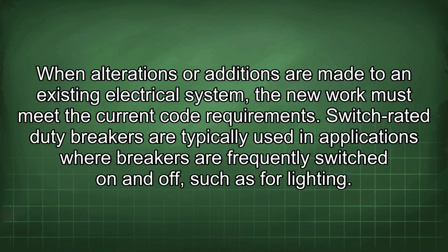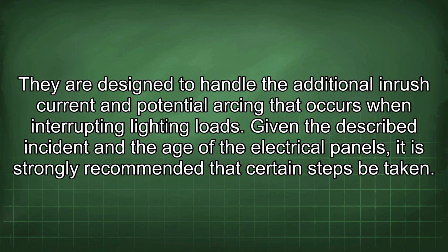Switch-rated duty breakers are typically used in applications where breakers are frequently switched on and off, such as for lighting. They are designed to handle the additional inrush current and potential arcing that occurs when interrupting lighting loads. Given the described incident and the age of the electrical panels, it is strongly recommended that certain steps be taken.